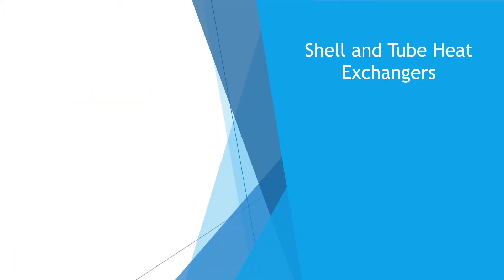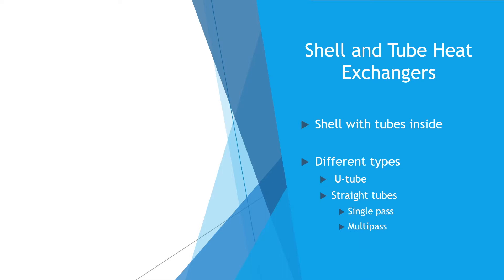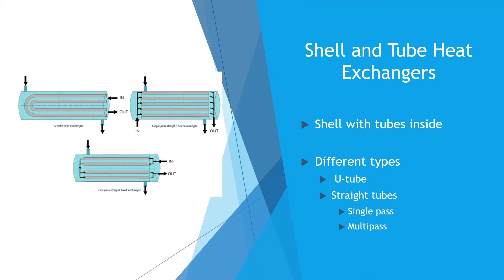Shell and tube heat exchangers are also popular, especially in industry. They are literally shells with tubes inside of them; the fluids flow through the tubes. The tubes can either be in a U-shape, shown in the first image, or straight. Shell and tube heat exchangers with straight tubes can either be single-pass, where the fluid goes in one end of the tube and out the other, or multi-pass, where the fluid enters and exits on the same side.